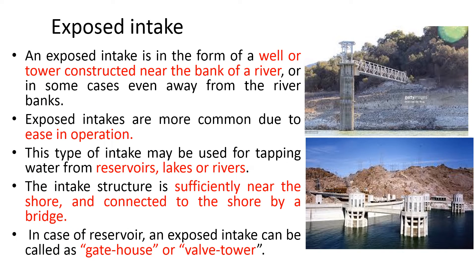The exposed Intake tower is connected with a footbridge over which the withdrawal pipe is provided. This is a widely used kind of Intake structure due to its ease in operation and can be used for any source. It is generally provided near the bank of a river, or if farther away, a footbridge is provided. In the case of a reservoir, the exposed Intake can be called a gatehouse or valve tower. Water is taken inside the tower, connected with the suction pipe, valves control the flow, and then it is transferred via the withdrawal pipe to the water treatment plant.